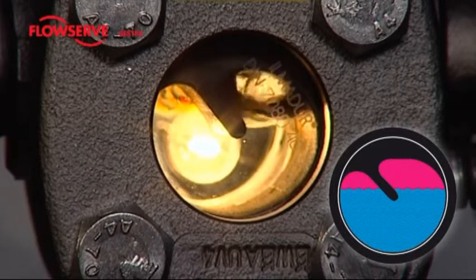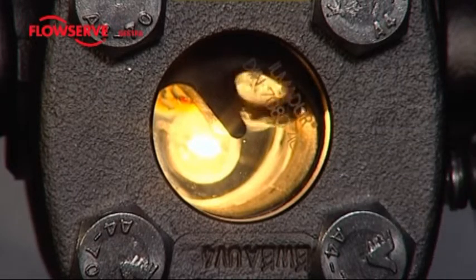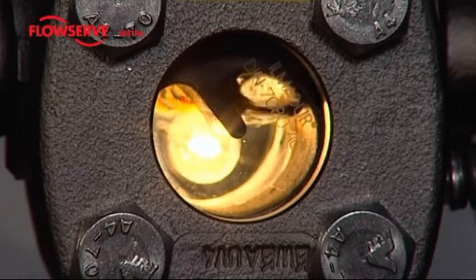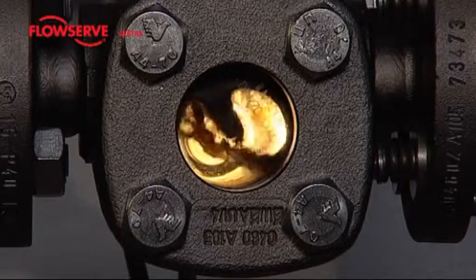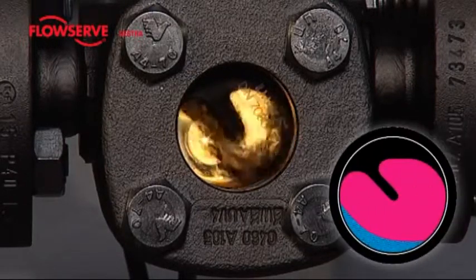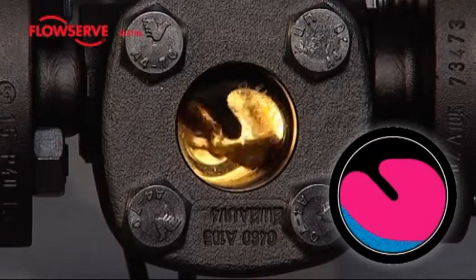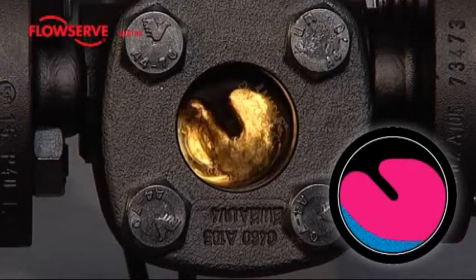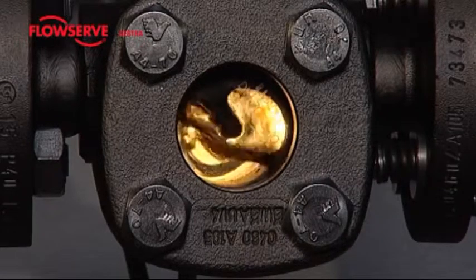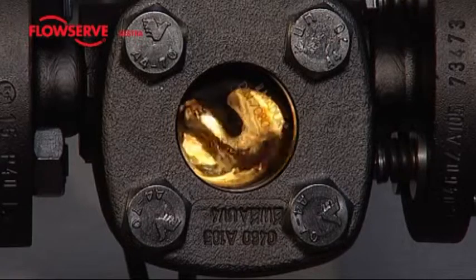The following steam trap is used for discharging only condensate. Steam does not pass below the deflector. Now the float trap is opened with the aid of its float lifting lever, so that steam is forced to flow through the steam trap. The deflector immediately emerges from the water, since the steam passing through now presses the condensate downwards into the siphon. This is a clear indication that the steam trap is causing loss of steam.